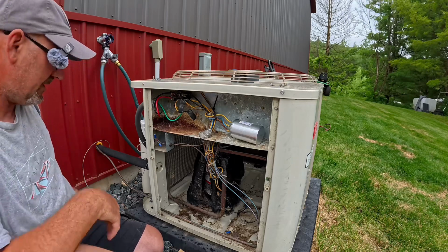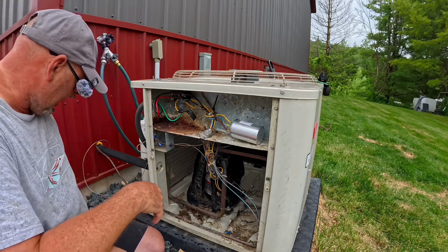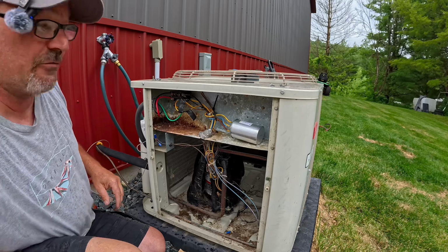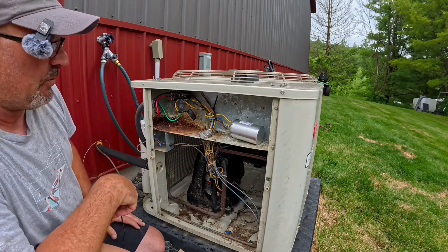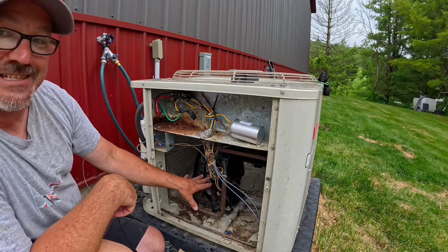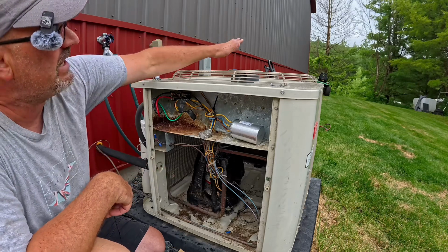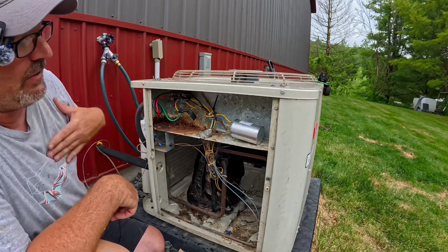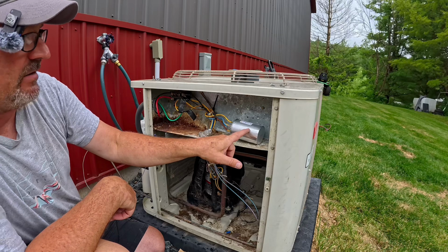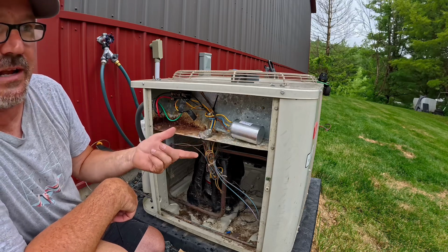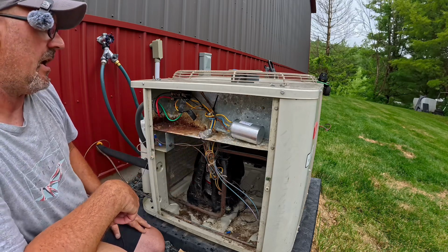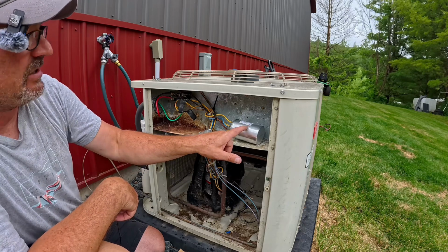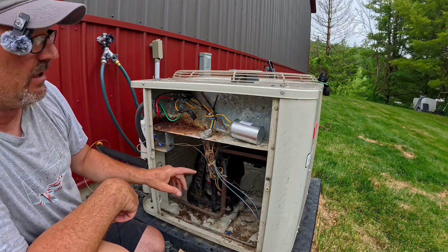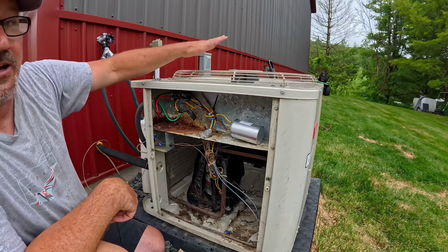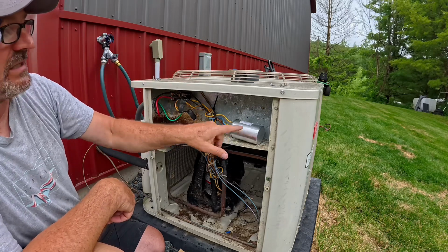Alright, this is the inside of an old air conditioner that works really well. That's why we haven't replaced it. So it's pretty simple what you have in here. We have obviously the AC compressor. We have the condenser fan located up here. We have what they call the run cap right here. It can be a start cap and it can be a run cap, or it can be a combination of 2. This is a combination capacitor, so it runs the AC compressor, and it also runs the fan. We'll get more into this in a little bit.